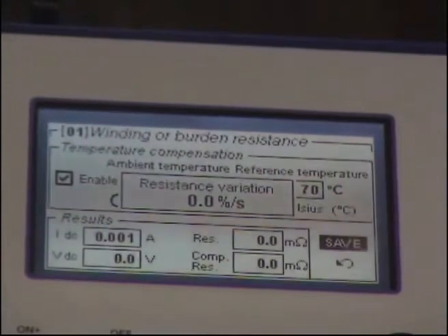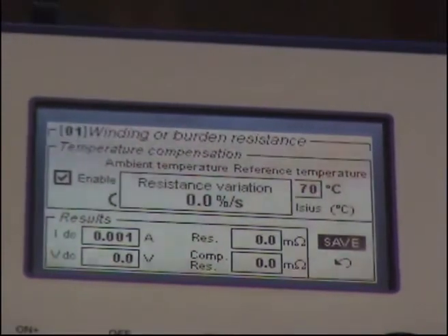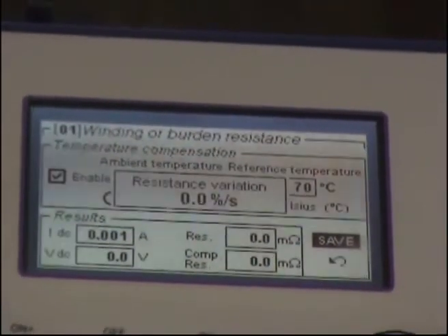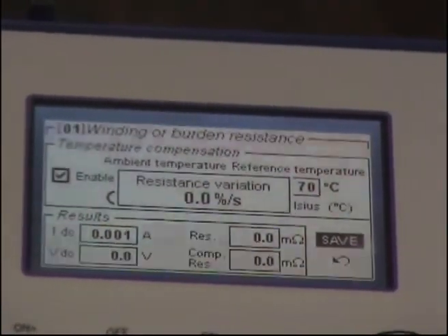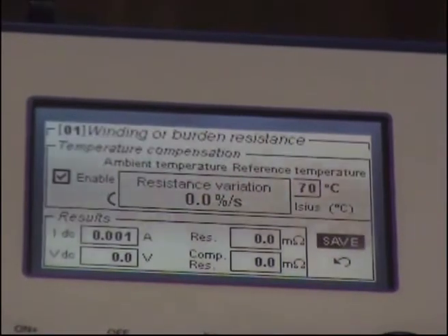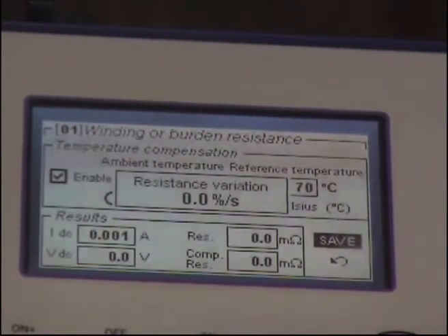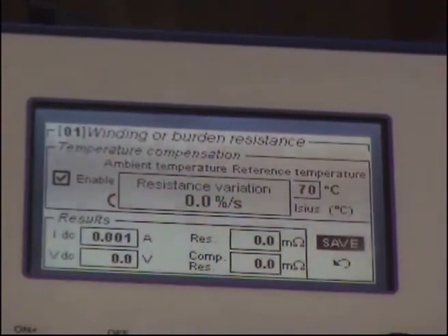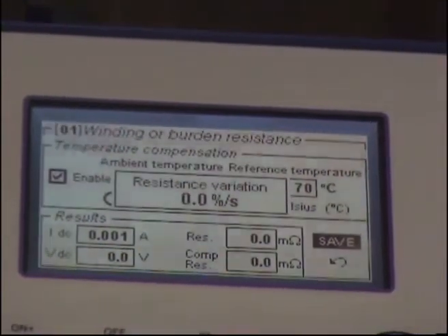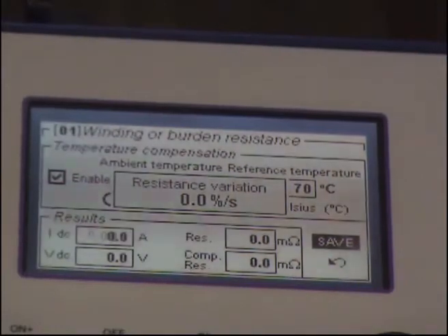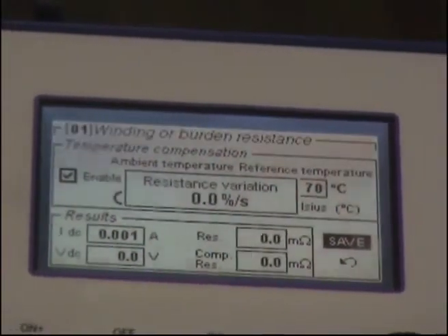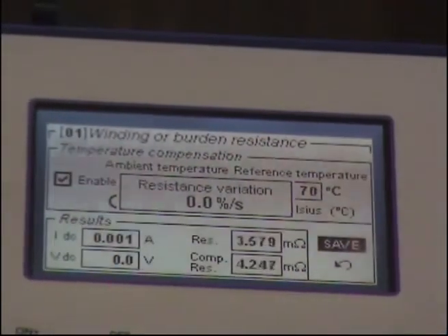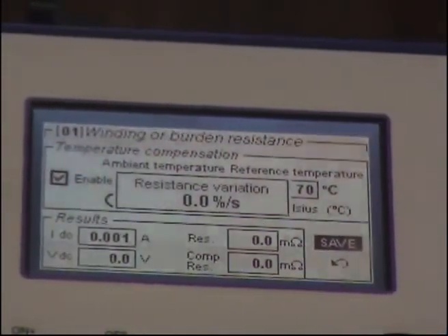And by the way, this inductance in big transformers is so big that you are close to being unable to perform the test. Anyway, with big transformers, the way to improve the situation is to short circuit all other windings unless the one that you are testing. Okay? Now, this is a small current transformer, so I don't do anything. Otherwise, I should short circuit the primary side.